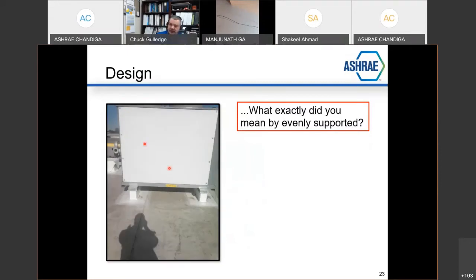This has a protective barrier over the fins on the condenser coils. Look at these roof supports. These should be lined up where the equipment is designed for the point loading to take place. These got installed in the wrong place.